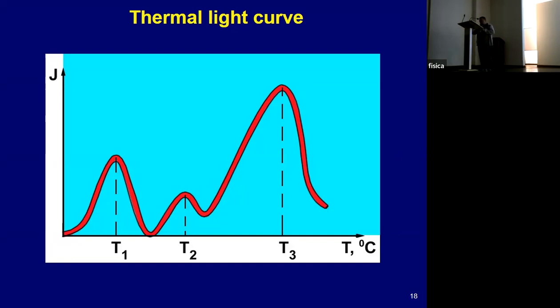The peak method is free from this shortcoming and has an advantage in measuring low doses. But this method is more sensitive to the heating regime or mode. For subsequent use, thermoluminescence detectors are heated again at a high temperature, up to 400 degrees Celsius, to completely free the residual capture centers.